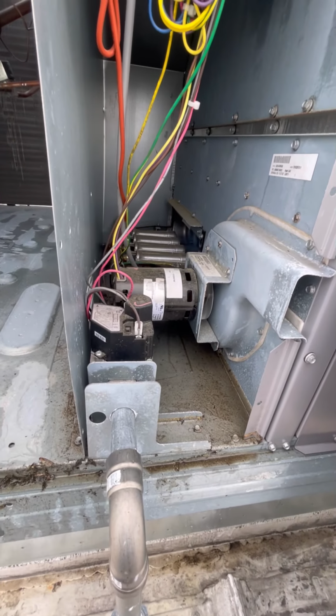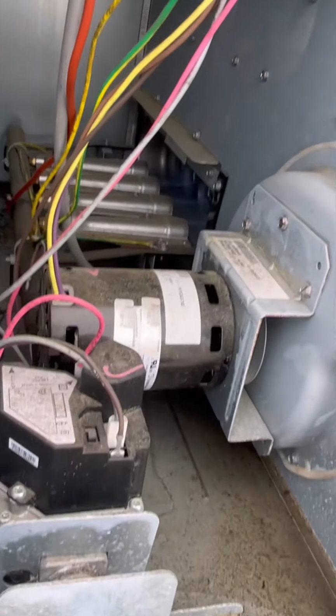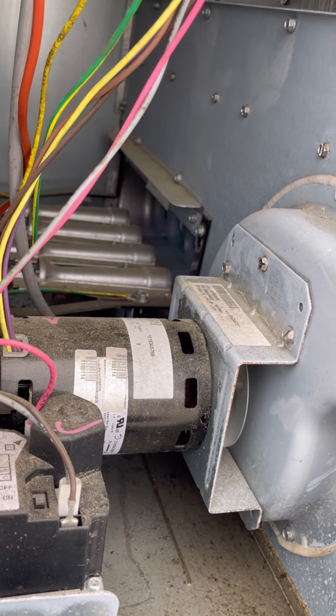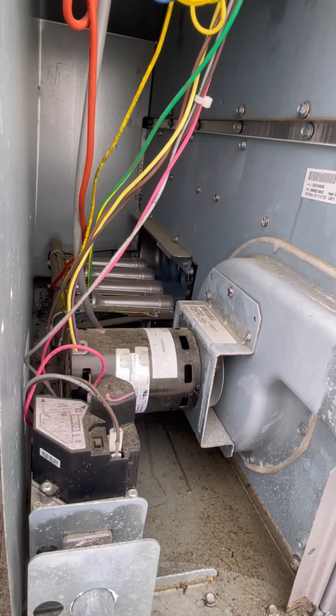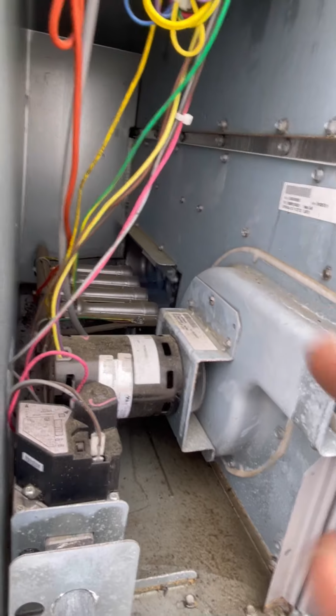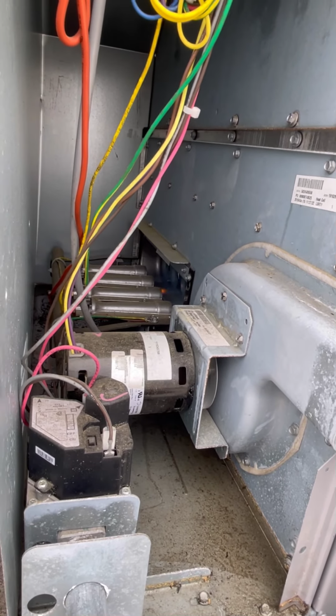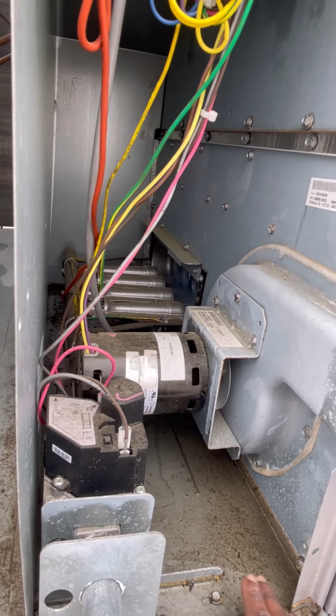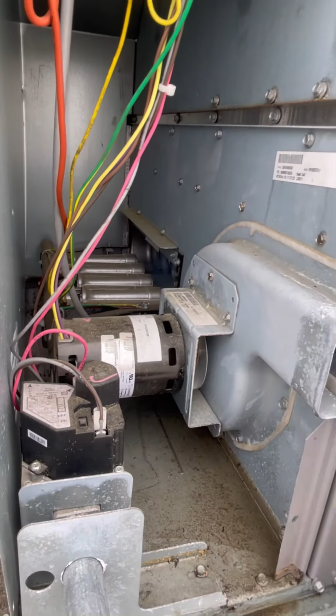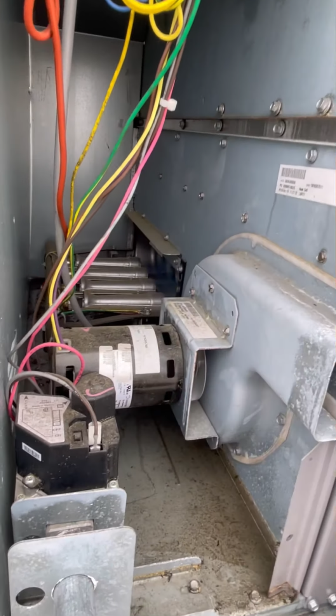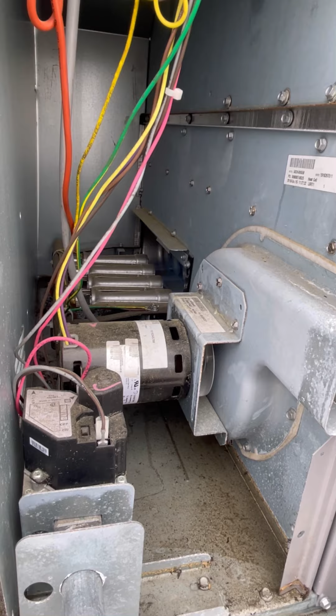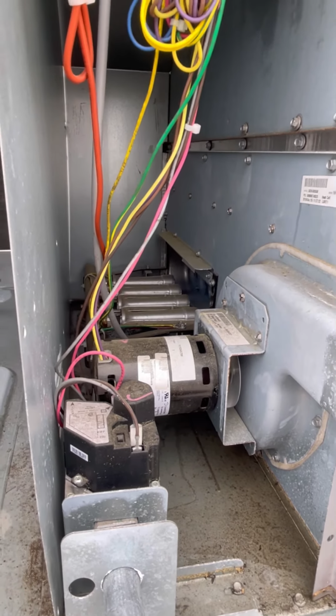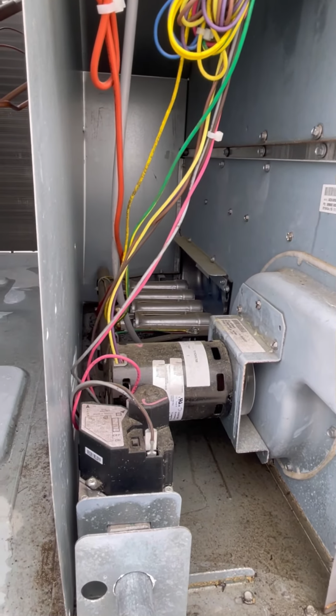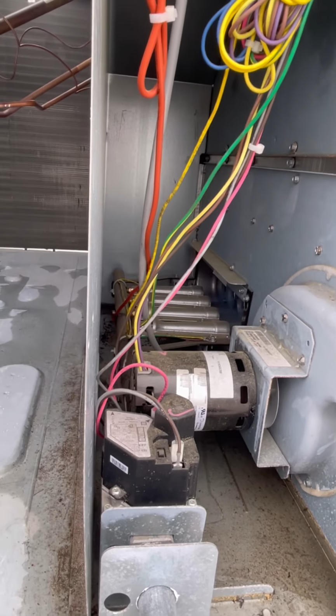Everything is testing like it should be. Back there you can see our flame, it looks really, really strong, not much orange in it. Sometimes you may see little orange flakes from dirt like this at the bottom of it, or air getting sucked in there right now, so dust and all types of stuff can get up in there and cause that. This wouldn't have fired on if all of the other safety mechanisms were to crap out. So that tells me everything looks good and everything's working as it should.